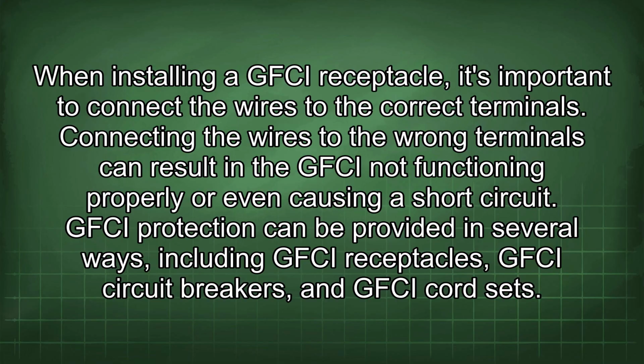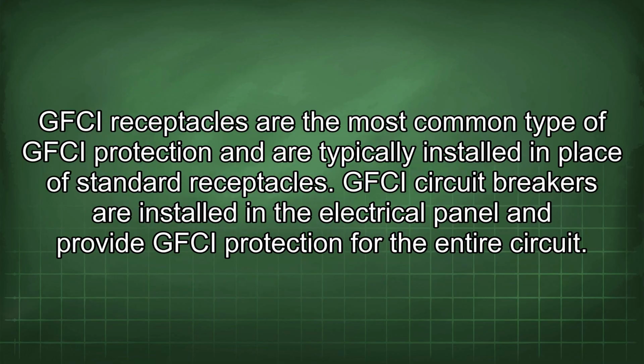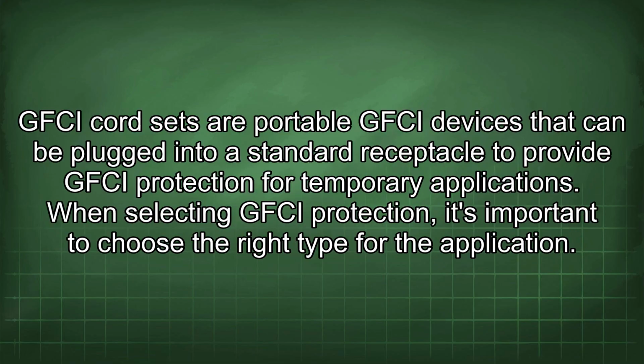GFCI protection can be provided in several ways, including GFCI receptacles, GFCI circuit breakers, and GFCI cord sets. GFCI receptacles are the most common type of GFCI protection and are typically installed in place of standard receptacles. GFCI circuit breakers are installed in the electrical panel and provide GFCI protection for the entire circuit.